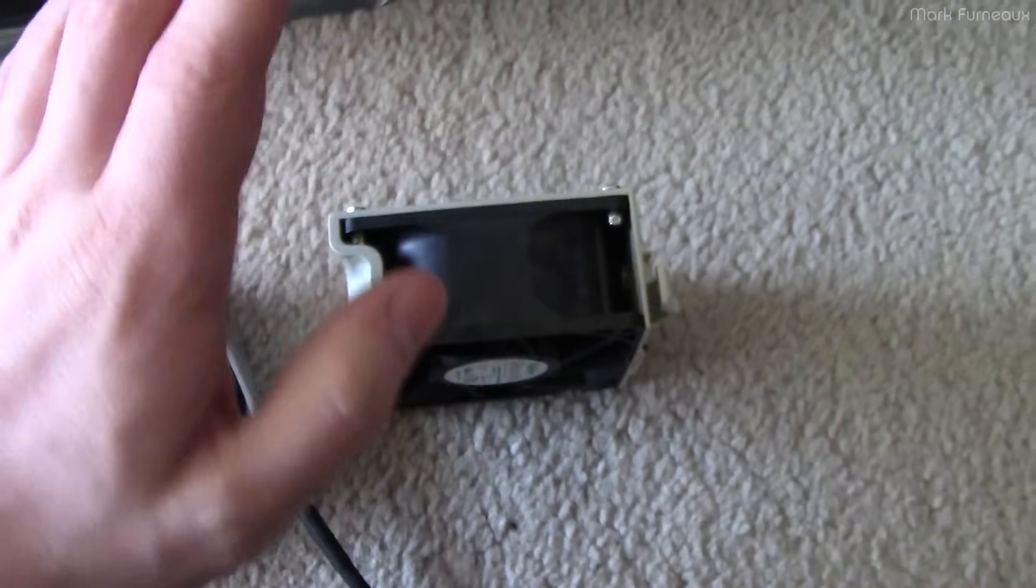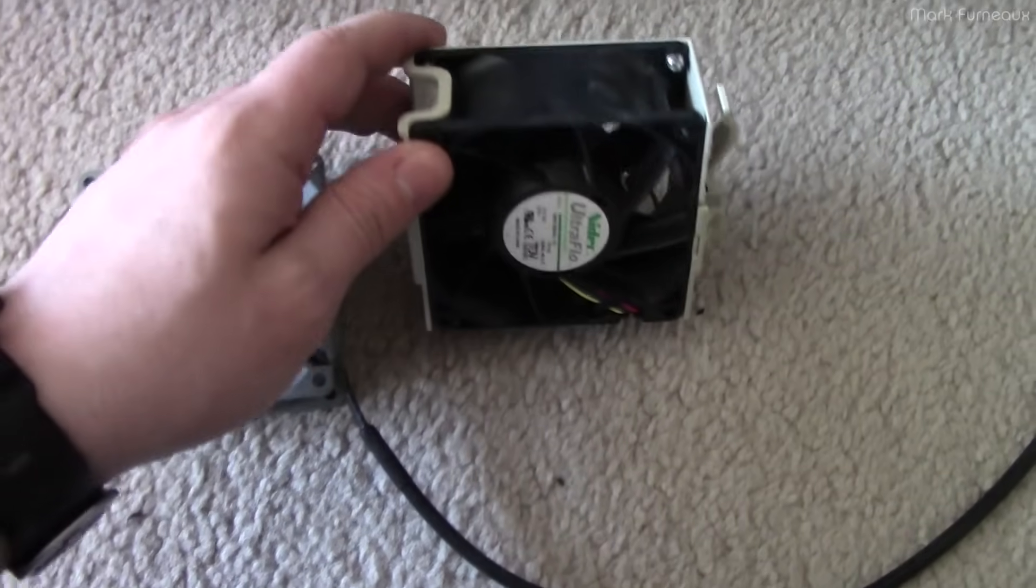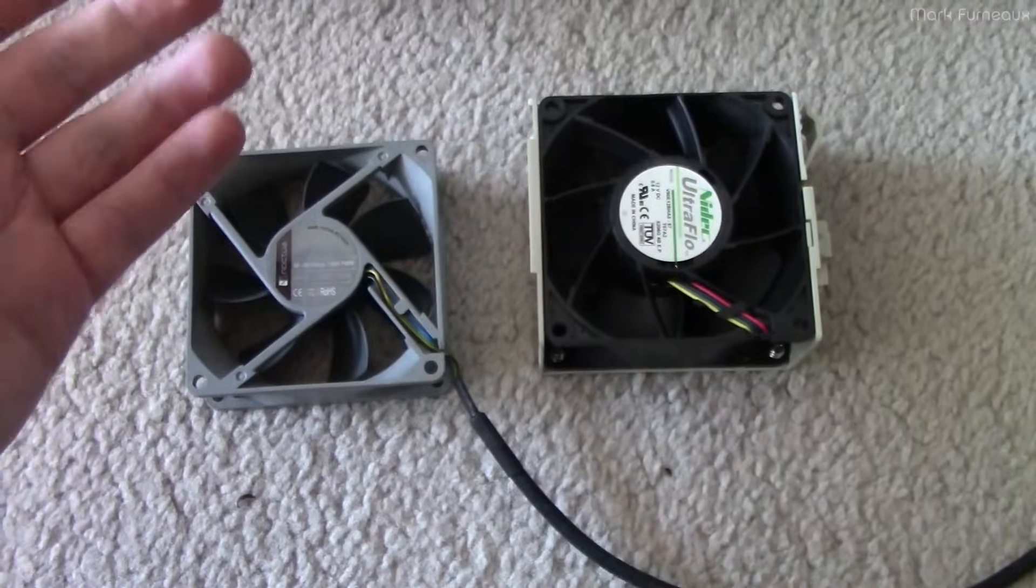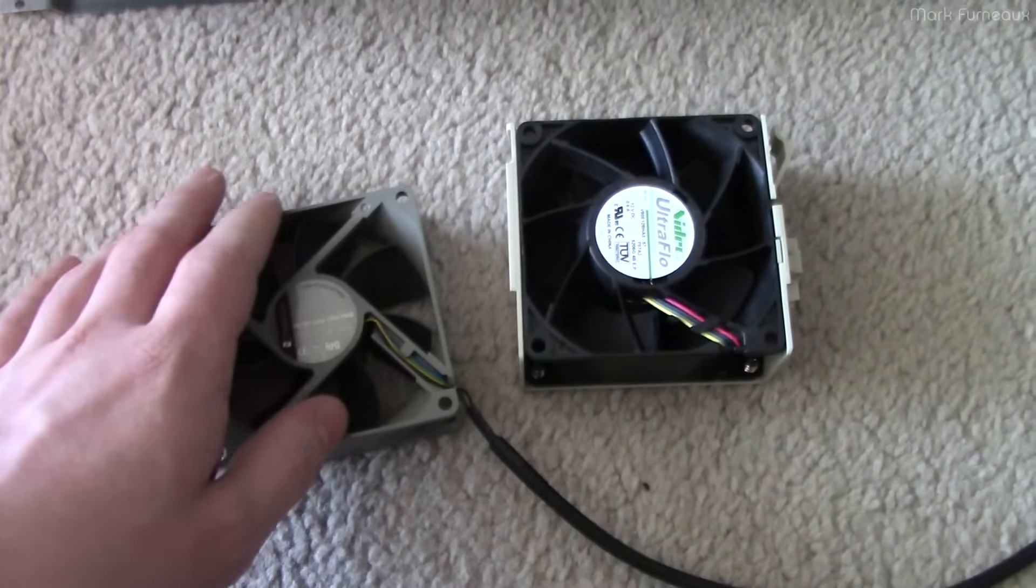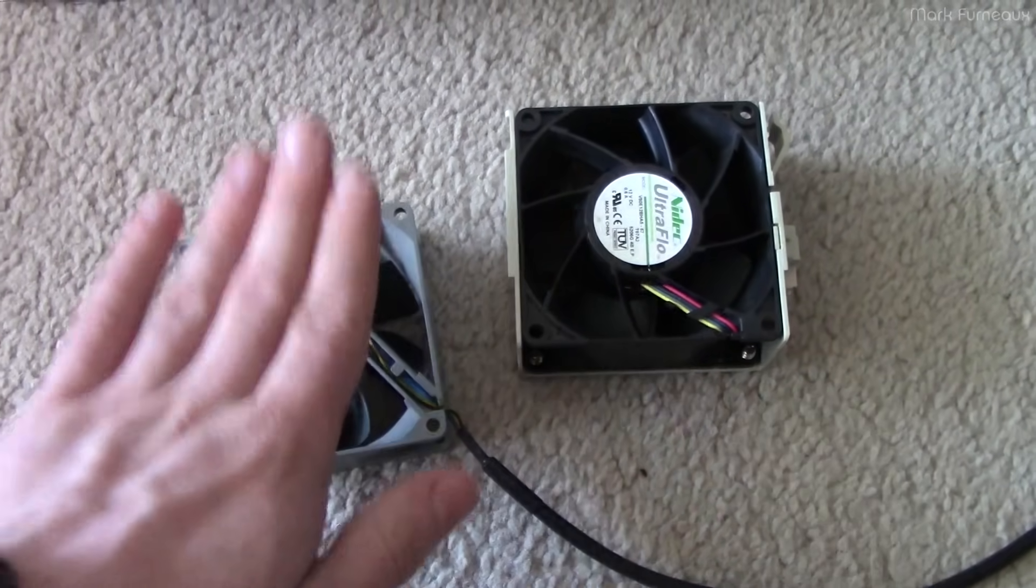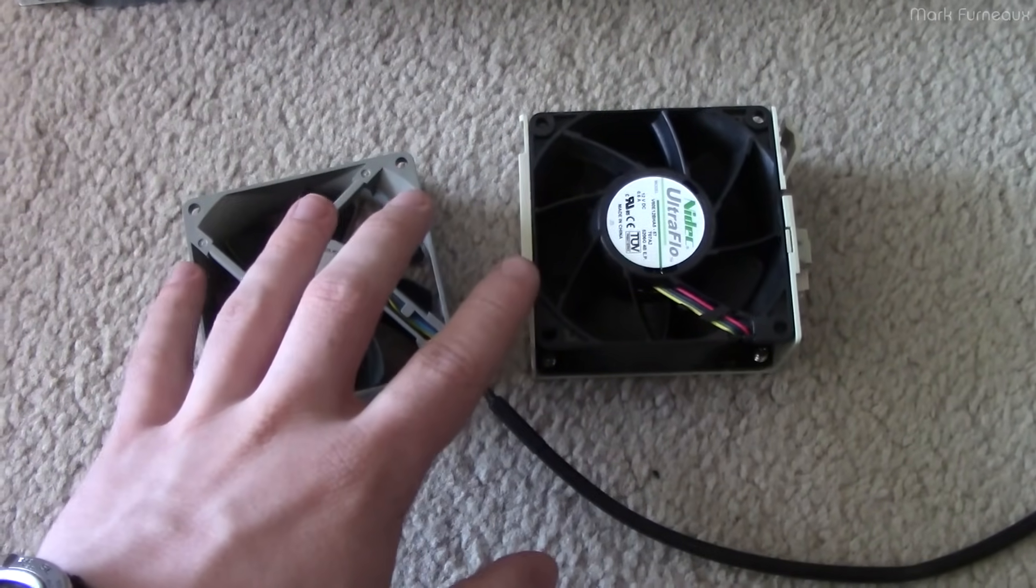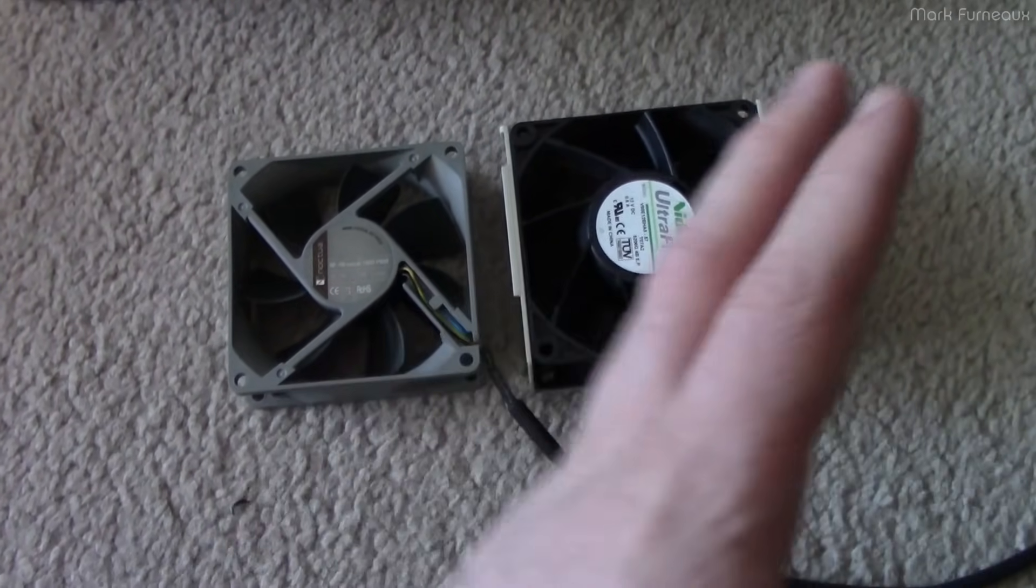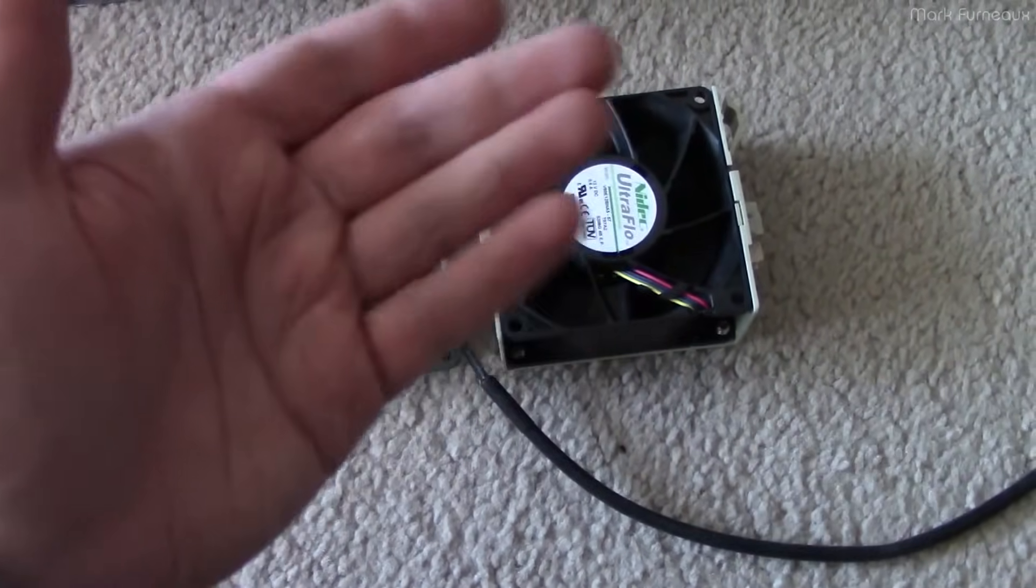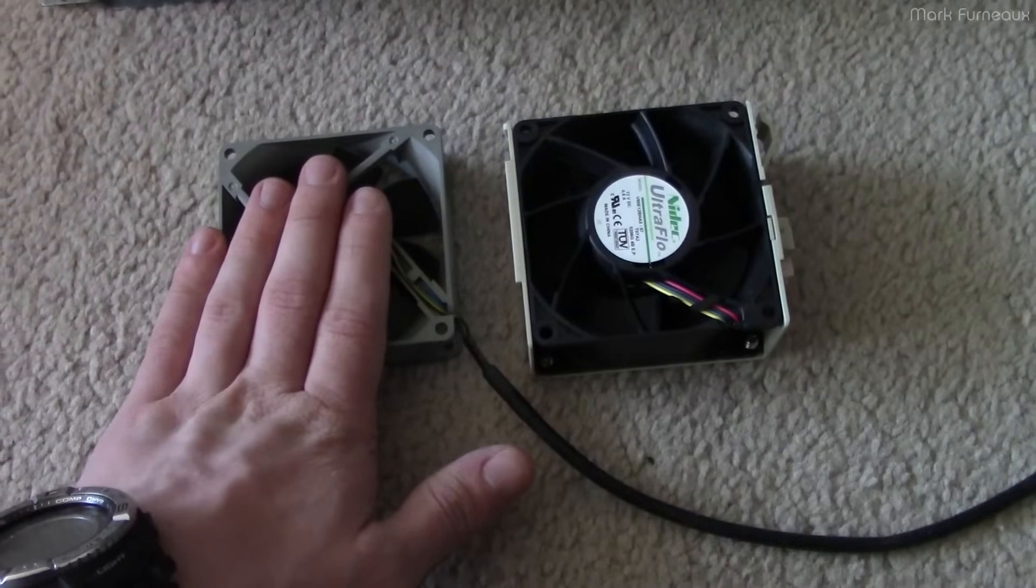So that's what I did. I originally made a bunch of fans with 80 millimeter consumer desktop fans. And it had two problems, one of which was, the primary one, it just wasn't enough airflow. That's going to be the biggest problem with trying to use quiet fans in a server chassis like this. The amount of airflow that comes out of these fans is just nowhere near what's necessary to cool the server, because this machine uses passive heat sinks on the CPUs. So it's two CPUs, and there's no fans on them, so it relies on case airflow. And it's got add-in cards of course at the end, and those add-in cards also don't have fans, so they require a certain amount of linear feet per minute to stay properly cooled. And these just could not produce that.